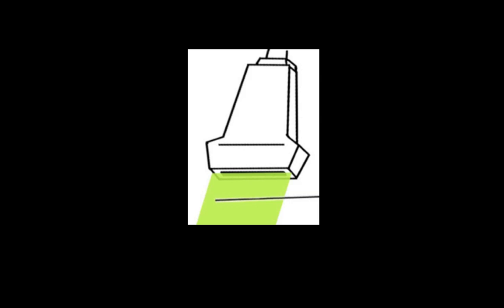So this is essentially what the ultrasound beam looks like. Two of its dimensions are fixed, so that the width of the beam is the width of the footprint of the probe, about 35 millimeters in our case mostly. And the depth of the beam, the anterior posterior depth as we look at it, is about 1 millimeter. And the length of the beam, the height of it, is adjusted when you adjust the depth settings. So you can imagine it almost as a credit card shaped object of variable length sticking out of the end of your probe.